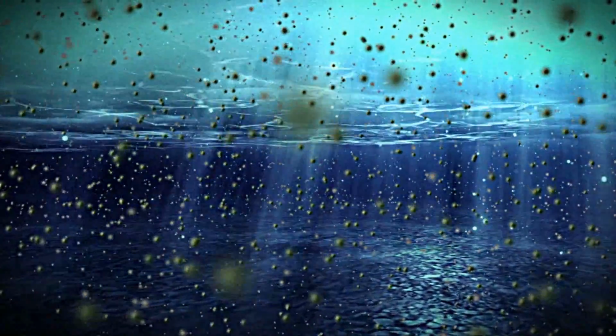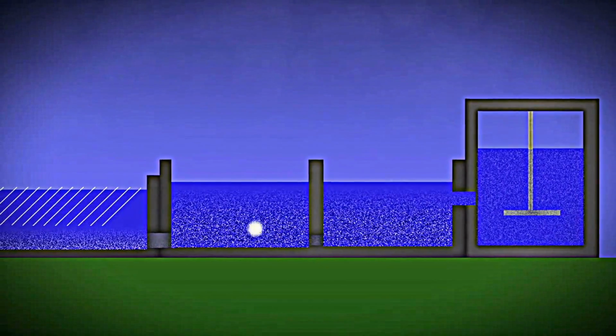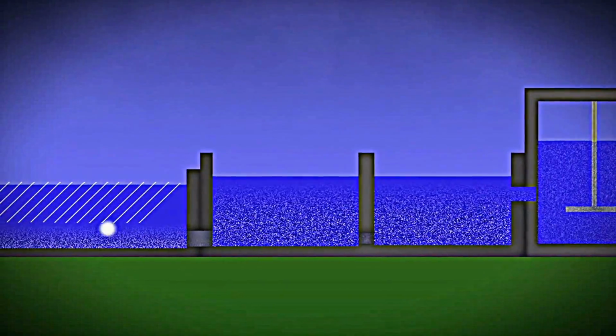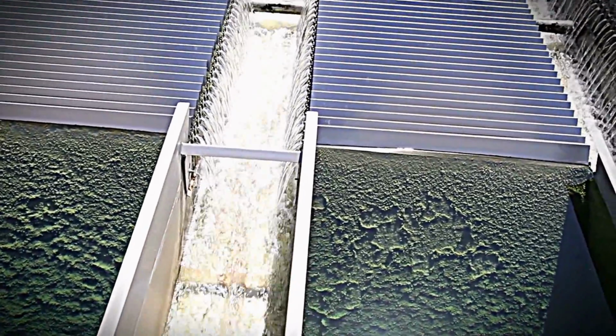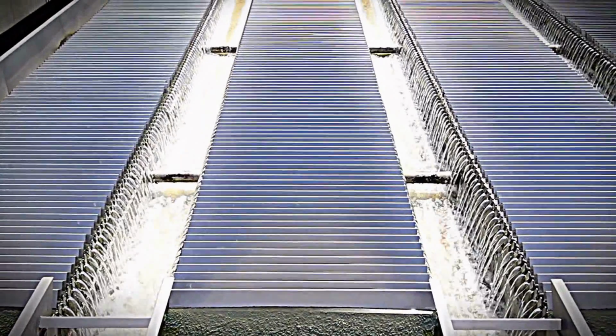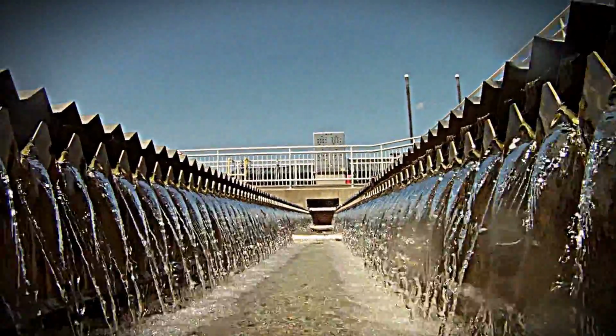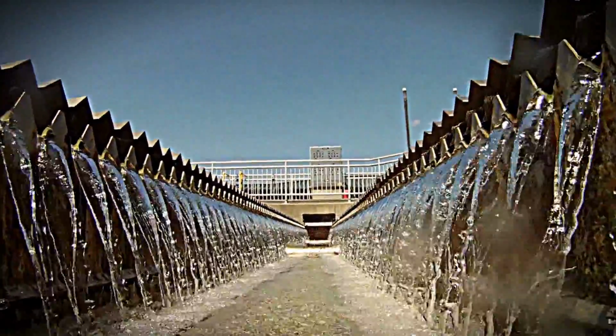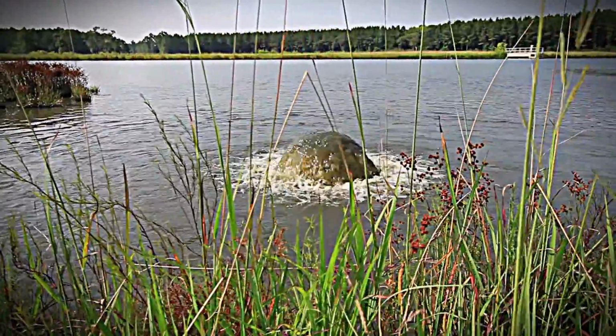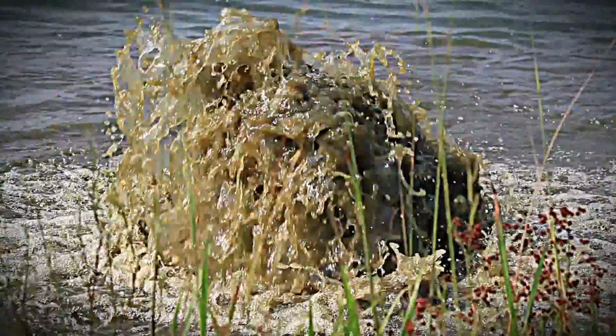As time progresses, the particles get heavier and begin to sink to the bottom. As the particles are sinking, the water flows into sedimentation basins. In the sedimentation basins, the impurities settle to the bottom, where they are collected by sweeps, and the clean water exits the top of the tank on its way to the next step of filtration. Here you can see the water, which by this step in the process is already 95% clean, rising out of the top of the weirs in the sedimentation basin. The impurities that were collected by the sweeps are later pumped out of the system into a holding pond.